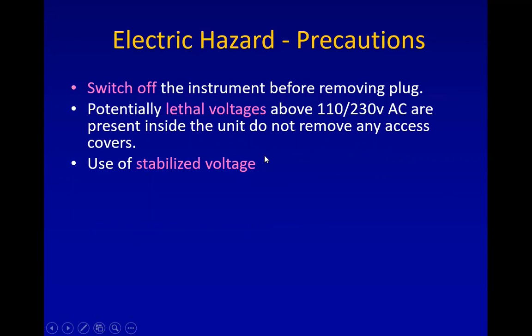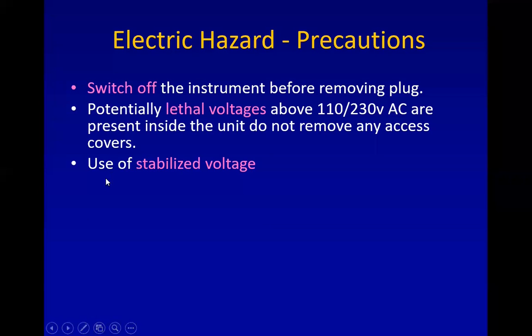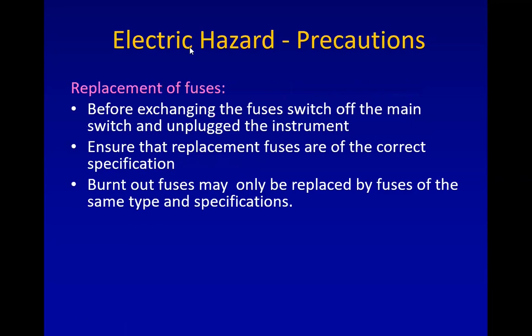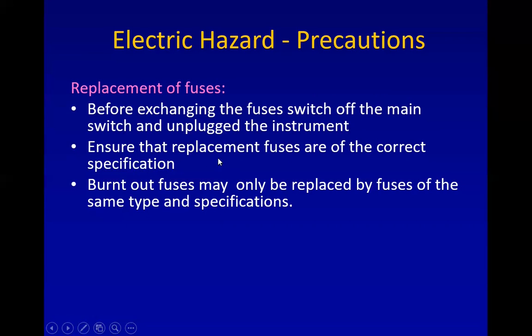Regarding precautions with respect to electrical hazards: the equipment should be switched off before removing the plug. Equipment usually works at a voltage of about 110 to 230 volts — 230 volts in India and 110 volts in some other countries — and both these voltages are lethal. It is recommended to use a stabilizer before the equipment. Whenever fuses need replacement, the equipment should be switched off from the main switch and unplugged, and the replacement fuse should be of the correct specifications.